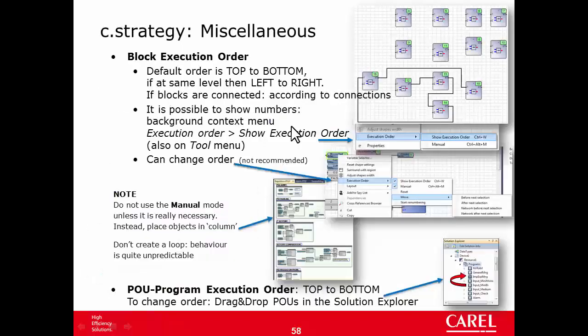If you know OneTool probably you noticed that over the blocks there aren't the numbers. So the question you may have is what is the block execution order? In c.strategy the order depends on the position of the blocks on the page. The order is top to bottom and if the blocks are at the same level from left to right. And then if the blocks are connected depends on the connection of the input and the output.